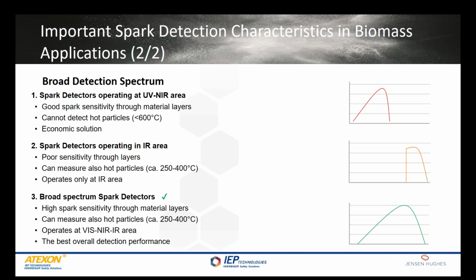At the same time, if we use a detector which is sensitive only to the visible or near infrared area, some ignition sources like hot particles cannot be detected. The best choice for biomass applications is broad spectrum spark detectors that can measure all radiation which doesn't belong to the protection area. That kind of detector can measure visible light, near infrared light, and also infrared light. In other words, it can measure hot particles, embers, flames, sparks, and many of them even through some material layers.